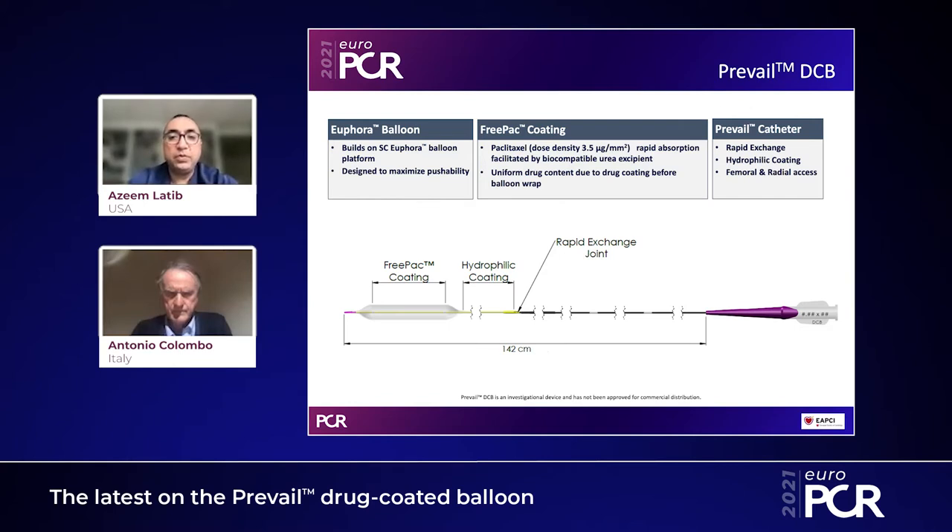The Prevail drug-coated balloon is a new drug-coated balloon from Medtronic that maximizes the technology used in Medtronic drug-coated balloons — the FreePac coating. The balloon has paclitaxel at a density of 3.5 micrograms per millimeter squared, facilitated by a biocompatible urea excipient, which leads to rapid absorption. There is uniform drug content throughout the balloon due to the drug coating that happens before balloon wrap. The coating and drug have now been placed onto the Euphora semi-compliant balloon, making this balloon extremely deliverable, even in complex lesions.